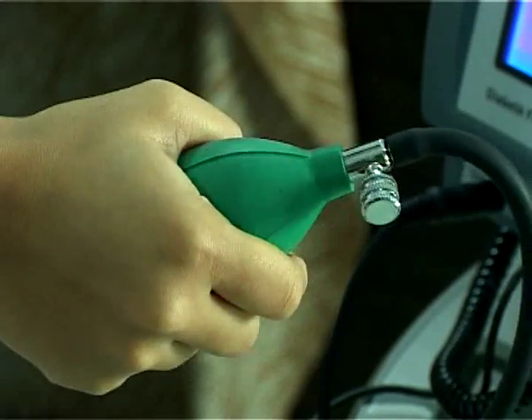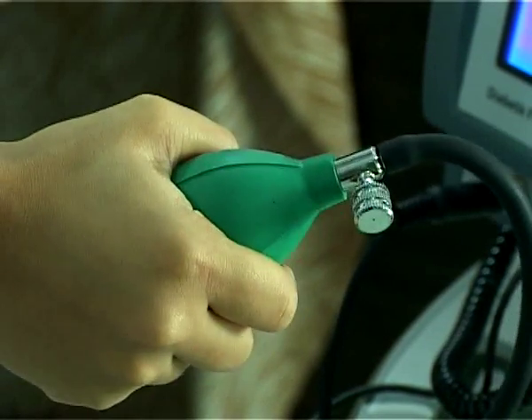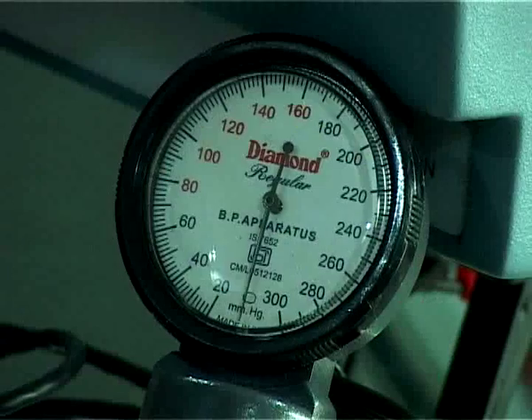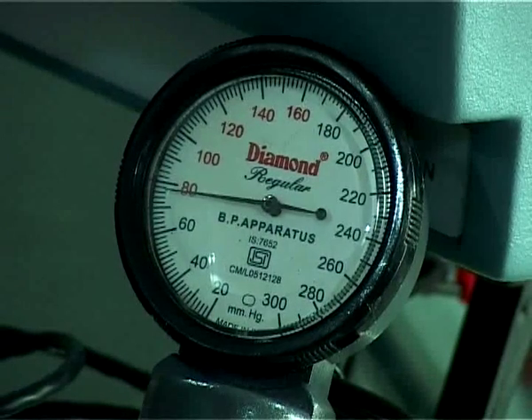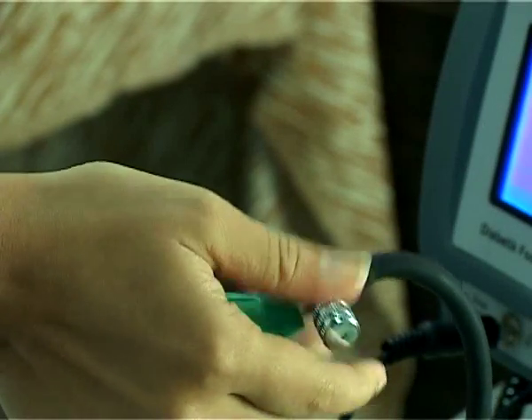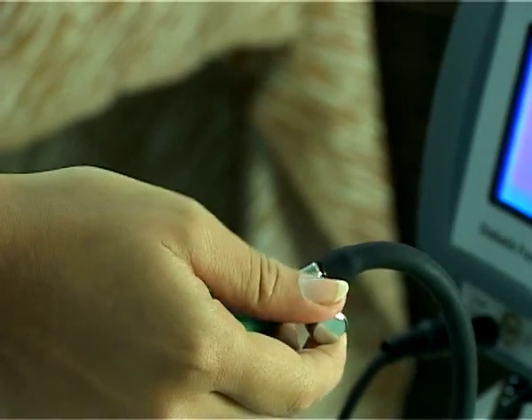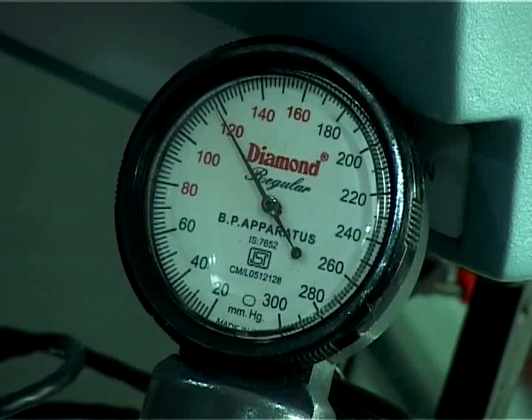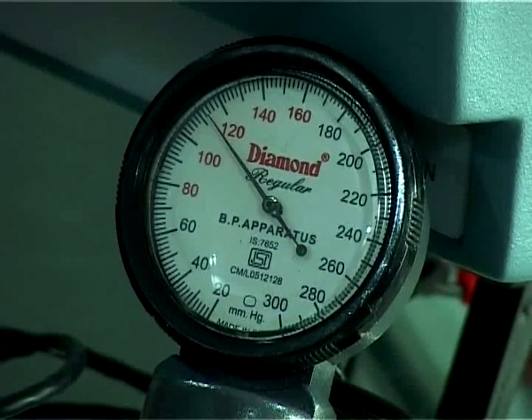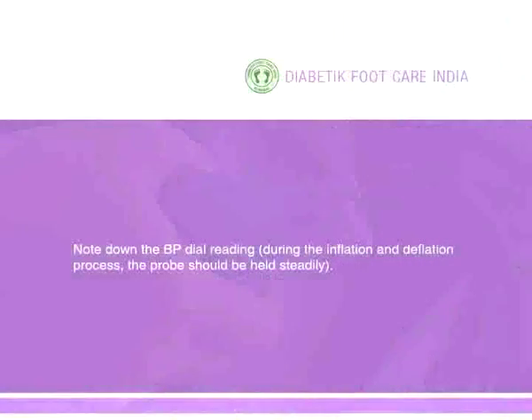Inflate the cuff until the Doppler pulsatile multiphasic sound stops. Slowly deflate the cuff and note the BP dial meter reading at the first reappearance of the sound. Note down the BP dial reading. During the inflation and deflation process, the probe should be held steadily.